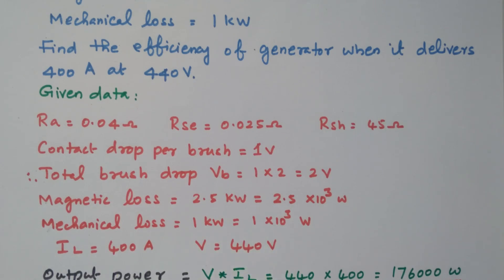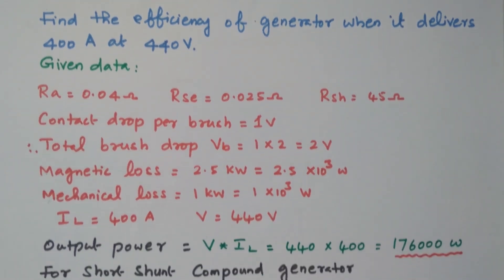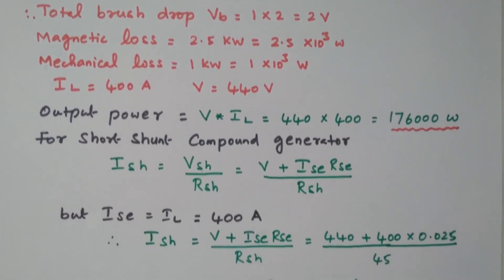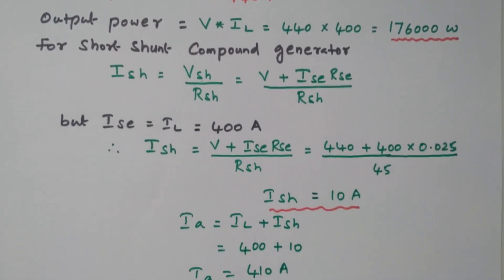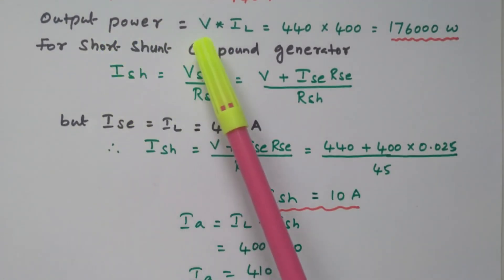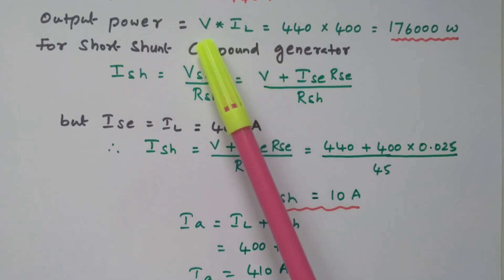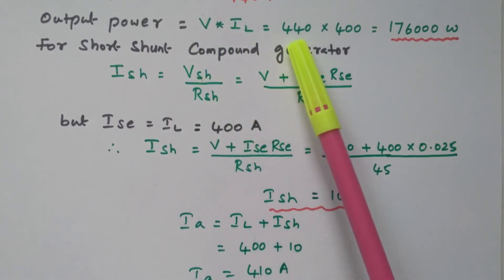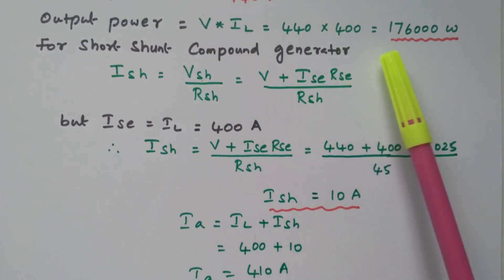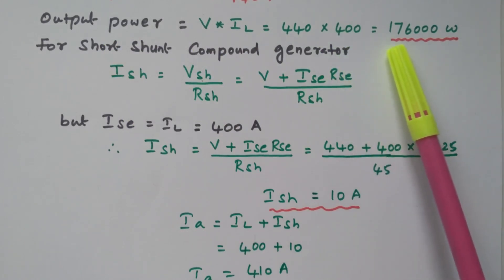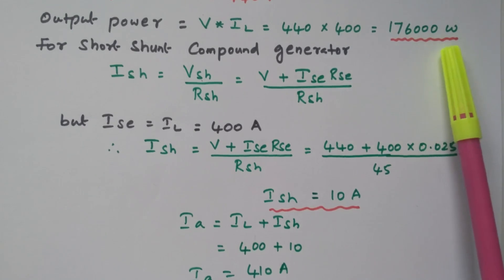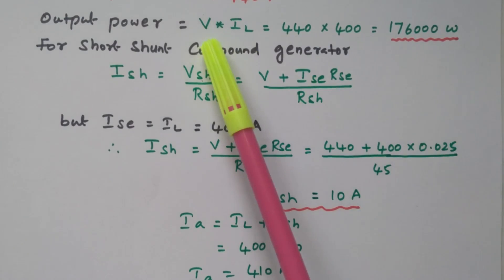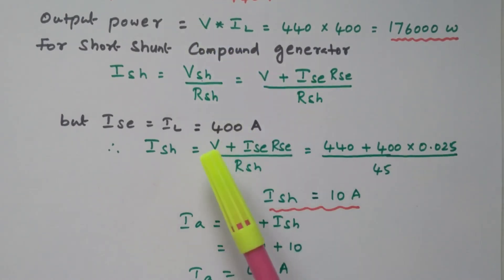Our final aim is to find the efficiency. First we will find the output power of this generator. Output power can be calculated from terminal voltage and load current: 440 volts into 400 ampere equals 176,000 watts. So 176,000 watts is the power output, calculated from terminal voltage and load current.